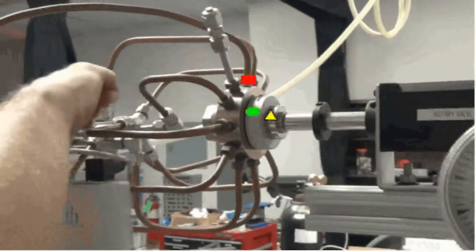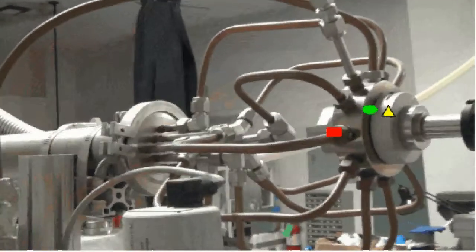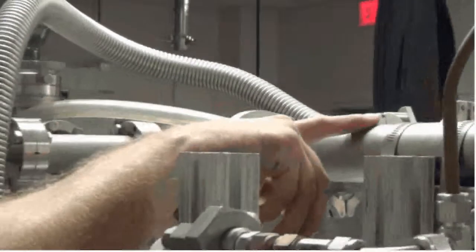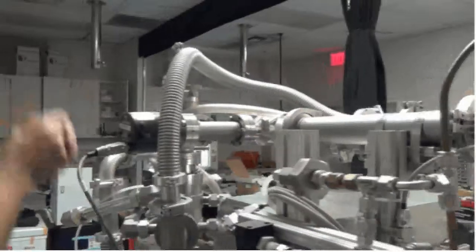This is a 9-position valve, and it lets us direct the flow into one of 9 differently sized orifices. The size of the orifice determines the flow rate through the instrument. And this flow rate, in conjunction with something called a critical orifice down here, determines what size of particles get focused into a particle beam.